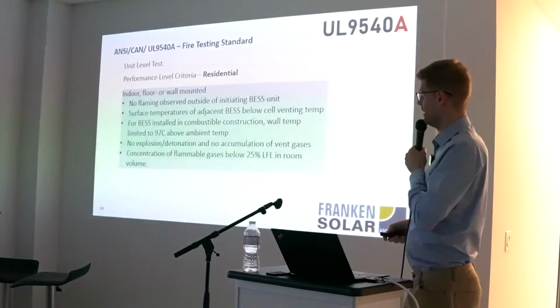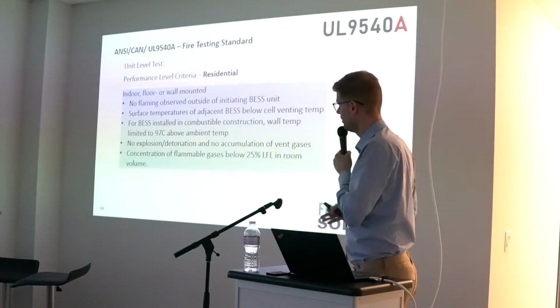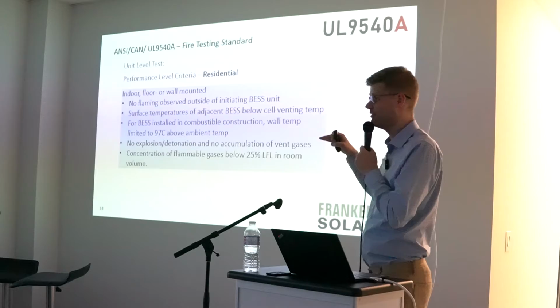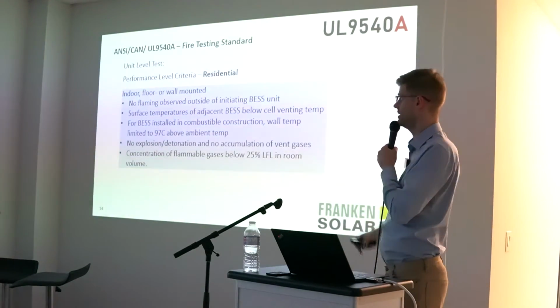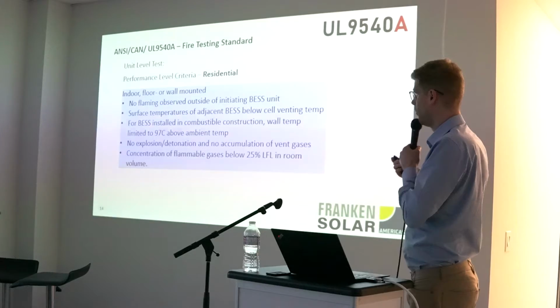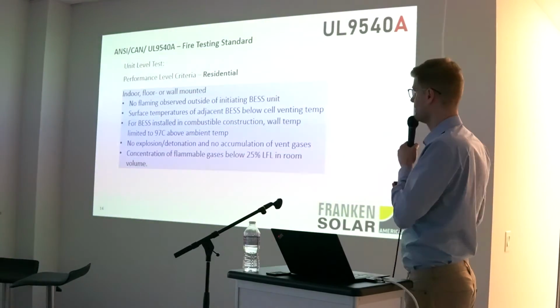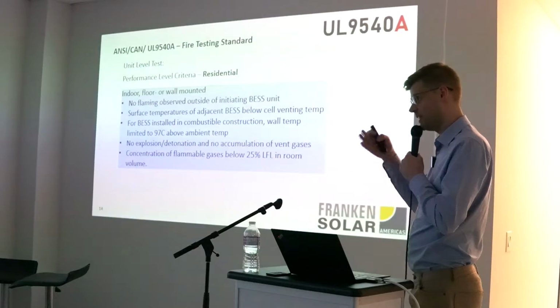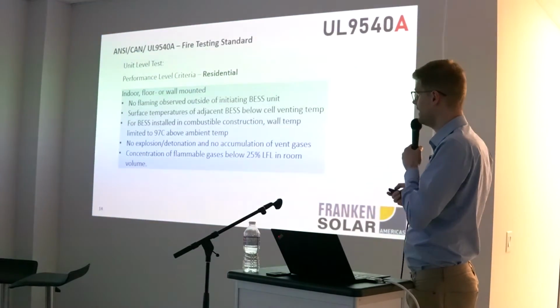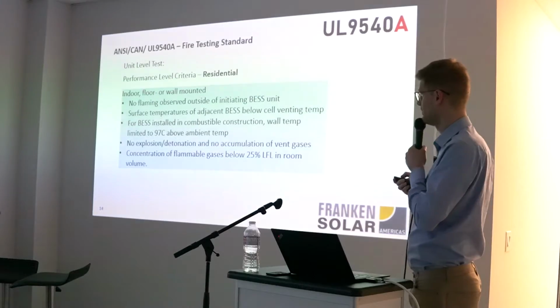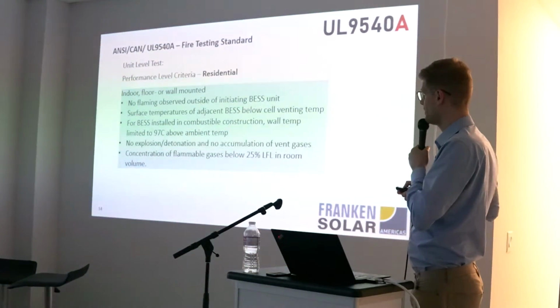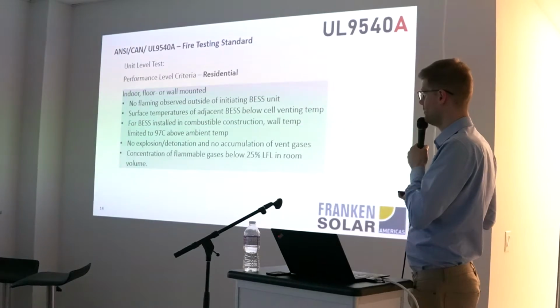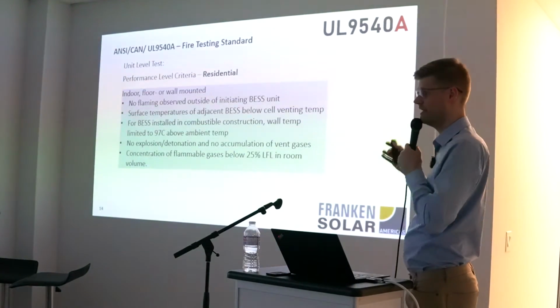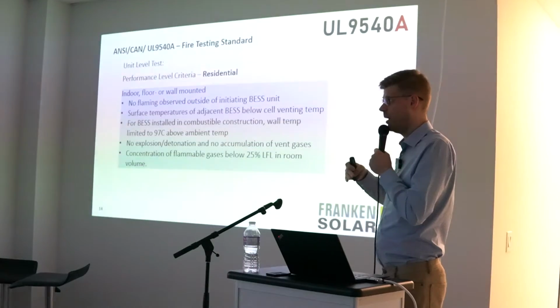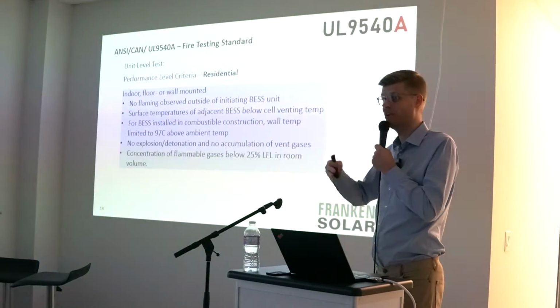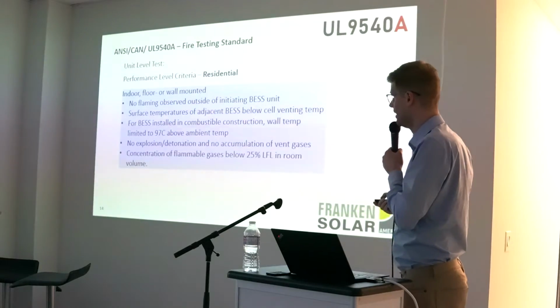Jumping right to the unit level of a system, we can divide the unit level into multiple different options. Let's start with the residential criteria. You can have floor or wall-mounted systems, typically indoors. All the cells in the module in the unit cannot have any flaming outside of the unit that comes out of the battery storage system. The surface temperature needs to be below the venting temperature, so they cannot ignite or heat up adjacent systems and adjacent modules.